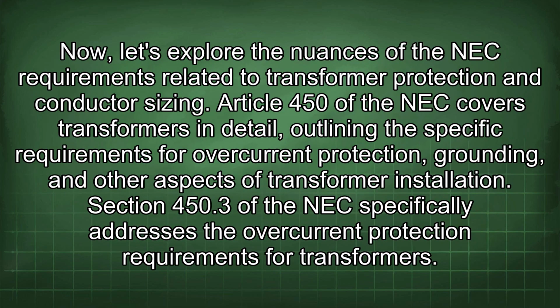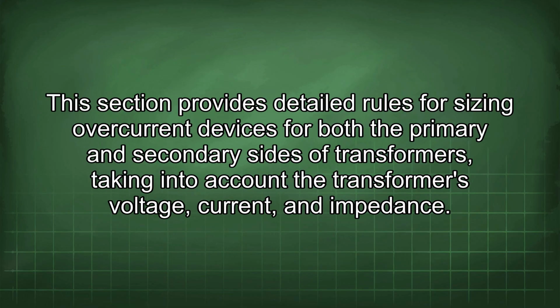Now let's explore the nuances of the NEC requirements related to transformer protection and conductor sizing. Article 450 of the NEC covers transformers in detail, outlining the specific requirements for overcurrent protection, grounding, and other aspects of transformer installation. Section 450.3 of the NEC specifically addresses the overcurrent protection requirements for transformers. This section provides detailed rules for sizing overcurrent devices for both the primary and secondary sides of transformers, taking into account the transformer's voltage, current, and impedance.